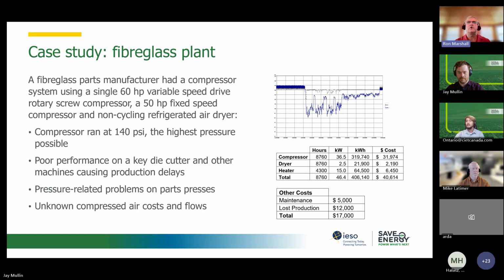And then we could see what components of the system were costing what amounts, right? We can see in that spreadsheet to the right, something to do with a heater, right? The fiberglass plant is very dusty. So their compressor room was fed with 100% outside air. And of course, around Winnipeg here, the air is getting pretty cold in the wintertime. They were using an electric heater to heat the air going into the compressor room, right? But they didn't realize that a compressor, you know, 80% of the energy going into a compressor comes out as heat. They could use the heat of compression to temper the air going into the compressor room rather than using an electric heater. So that 6450 cost was something that something could be done about, right?